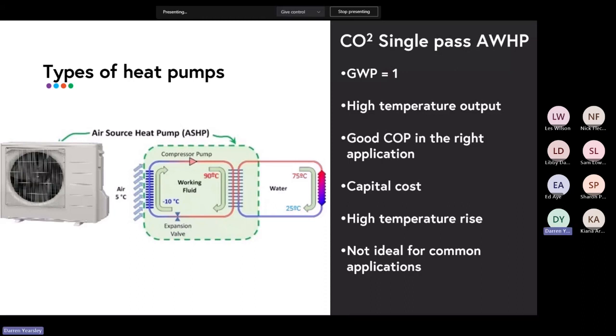Okay, so when we come to size systems with heat pump technology, it's a little bit different because your heat pumps are very, very expensive in terms of cost per kilowatt, and proportionally it makes the cost of storage much cheaper. And also when it comes to installing these appliances, it's much, much cheaper to put in a big gas pipe than it is to put in a big electrical infrastructure. So typically what we find with these jobs is you're always pushing for amps. You're always kind of jammed up in the maximum number of amps you've got available.